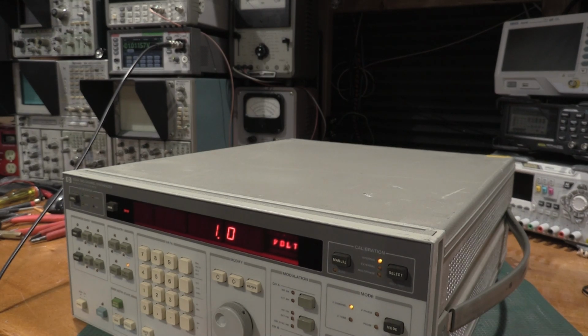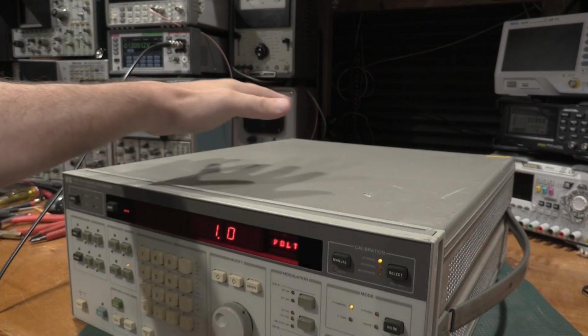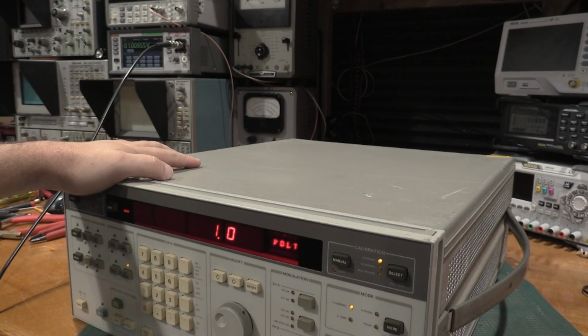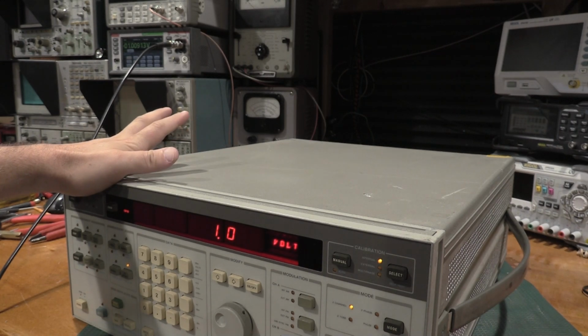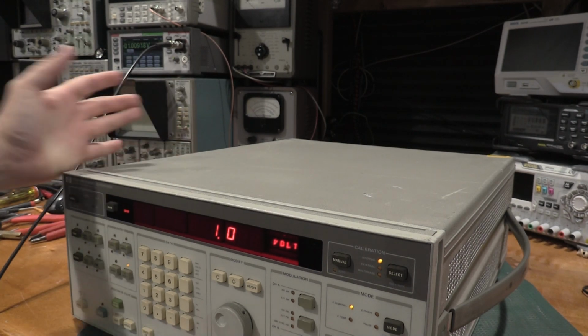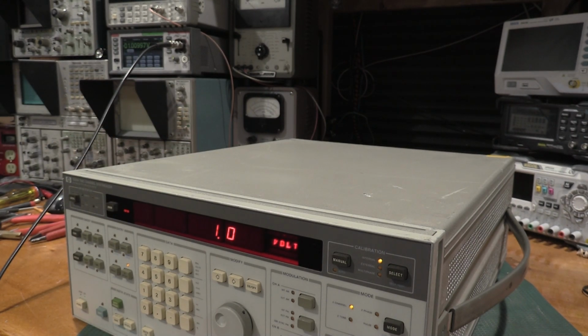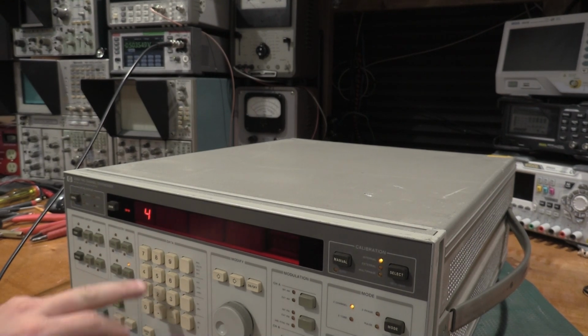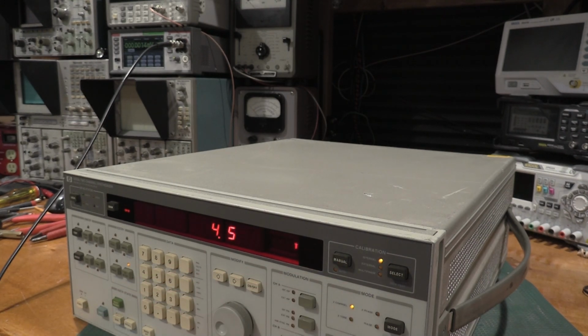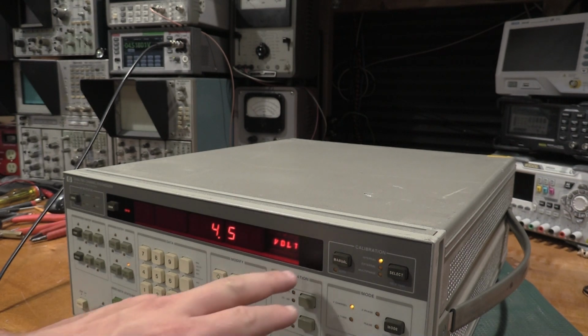There we go. So what we actually have is a relay contact resistance problem. It's not aligning because it doesn't have enough signal getting through some of the switching relays. When you hit this manual calibration button, a bunch of relays in this thing go kind of nuts, and it routes signals all kinds of places. There's a couple of relays, especially at the small signal side, where the contact resistance has gone high and it's not getting through correctly anymore. That's why when we do it at 1 volt, it works, but if I do it at half a volt, it dies. 4.5 volts, no problem, plenty of signal, everything gets through, or you make a liar out of me.